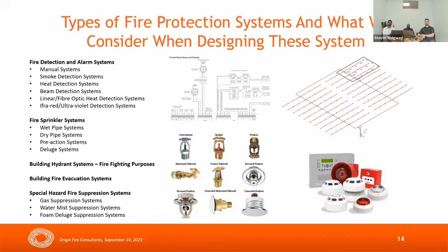What are the types of fire protection systems and what we consider when designing these? There's a significant amount of design, calculations, compliance requirements, and product knowledge required to produce a fire protection design. As we are limited on time, I'll briefly cover some overarching aspects of a few types of systems. There are various types of fire protection systems which may be required for a building. This includes fire detection and alarm systems. When designing such systems, we need to consider the appropriate type of detection suitable for a particular area within the building, with the intention of mitigating false alarms due to the normal operation within that building or area.